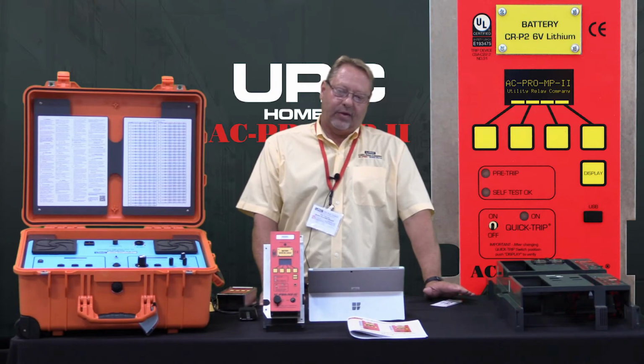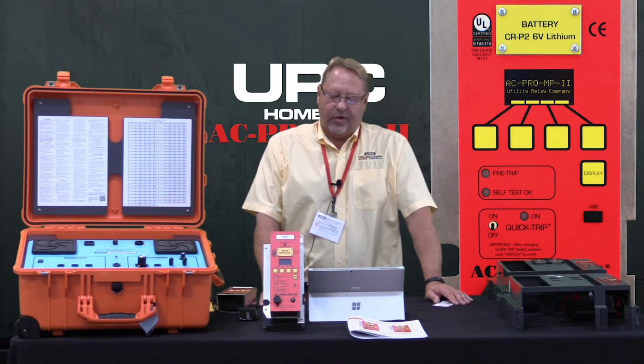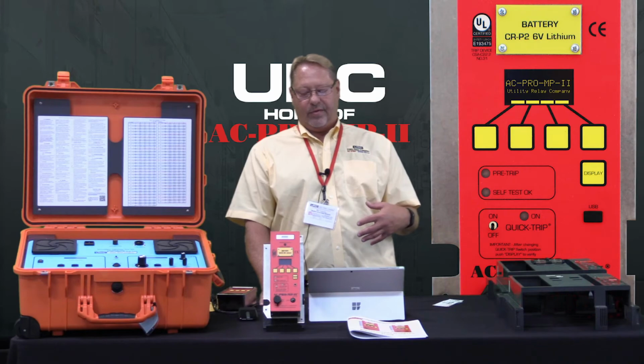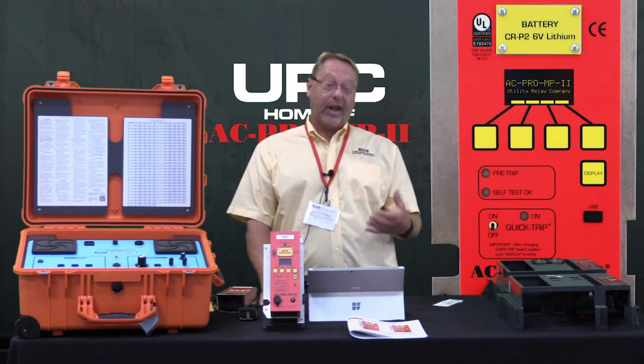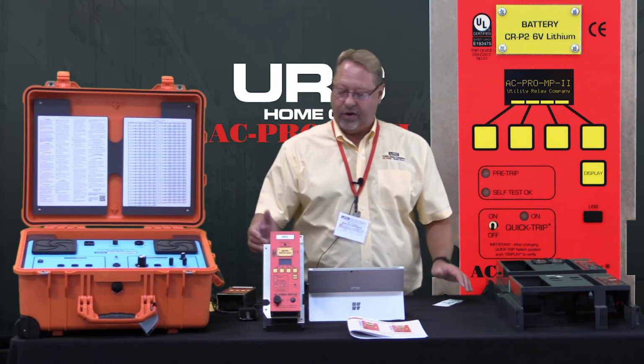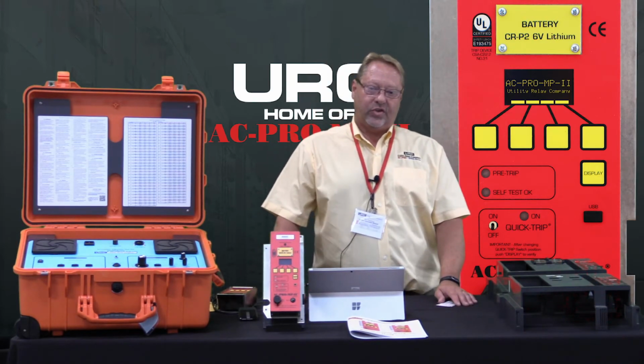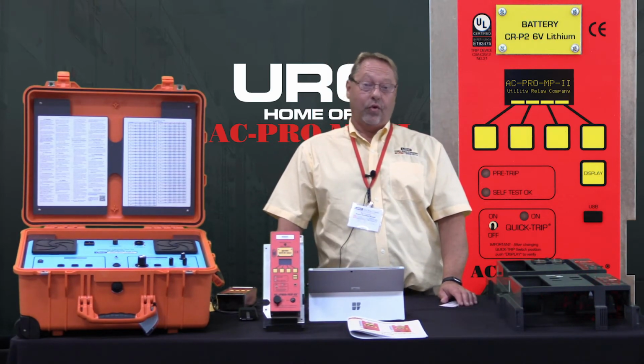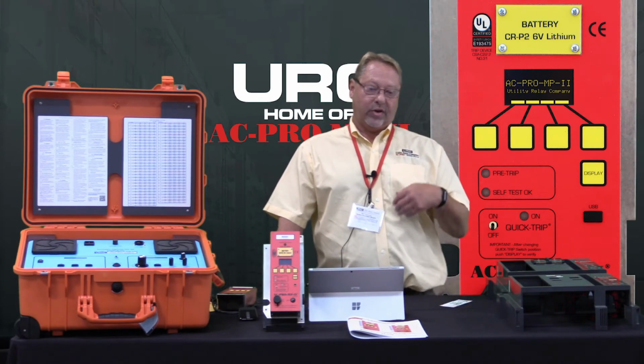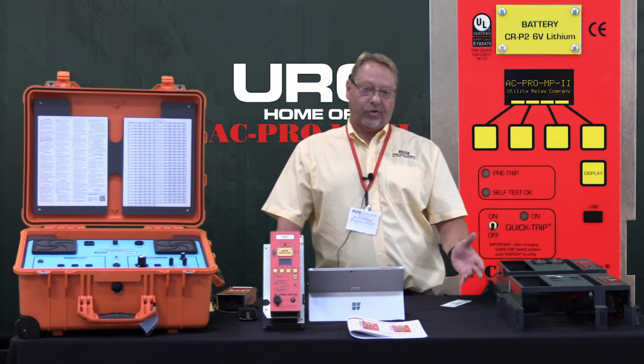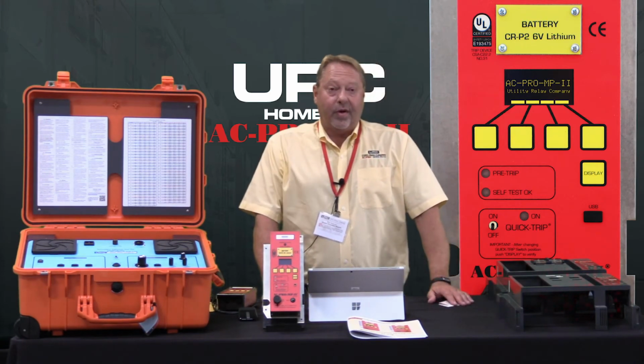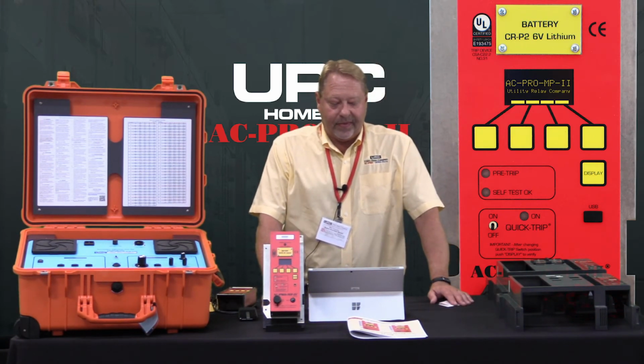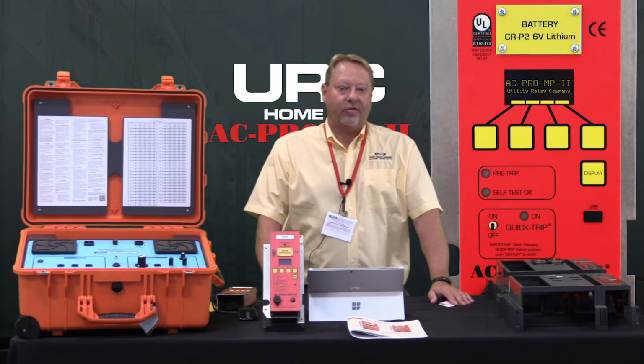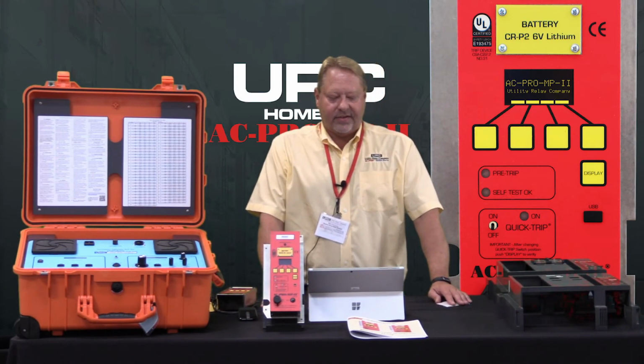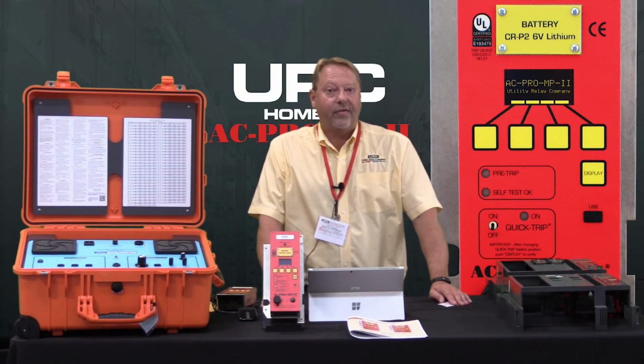Some people call it a maintenance mode. The maintenance mode allows you, if you're working downstream of a breaker, it's an area where it's dangerous. So by turning on the quick trip switch, you're basically switching in a different instantaneous or ground fault setting, allowing the breaker to clear faster to try to minimize the arc. The product is both UL and CE listed, and a secondary injection test set is also available. All of our products are made in America and manufactured at a facility in Chagrin Falls, Ohio.